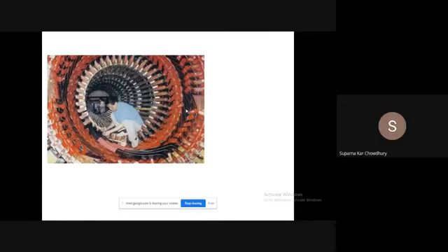So here also, normally mica is used for field insulation. But when we go for the salient pole machine, the stator winding normally has mica insulation. But for the rotor winding, the stress is not that great and the temperature rise is also not that large, so we can have other types of fiber insulation; that is sufficient, mica is not required.